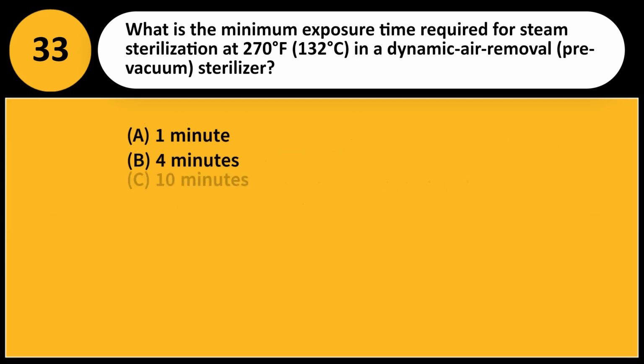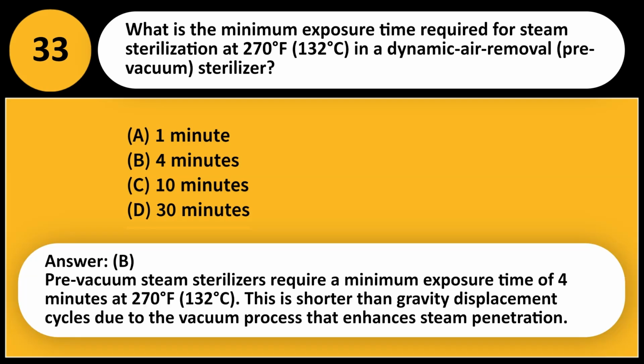What is the minimum exposure time required for steam sterilization at 270 degrees Fahrenheit, 132 degrees Celsius in a dynamic air removal, pre-vacuum, sterilizer? A. 1 minute. B. 4 minutes. C. 10 minutes. D. 30 minutes. Answer: B. Pre-vacuum steam sterilizers require a minimum exposure time of 4 minutes at 270 degrees Fahrenheit, 132 degrees Celsius. This is shorter than gravity displacement cycles due to the vacuum process that enhances steam penetration.